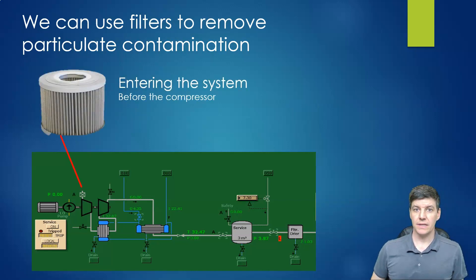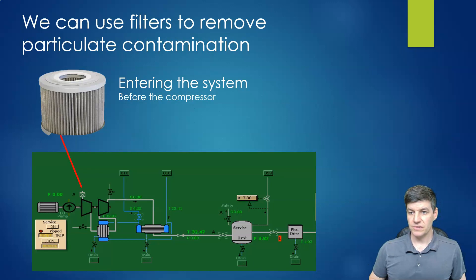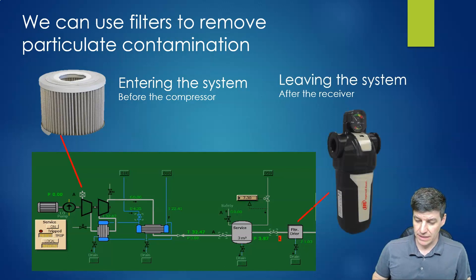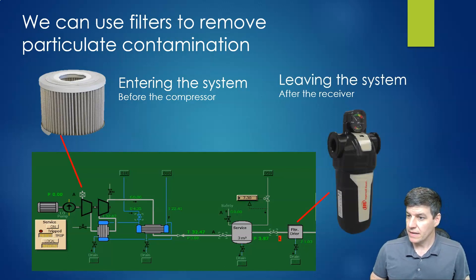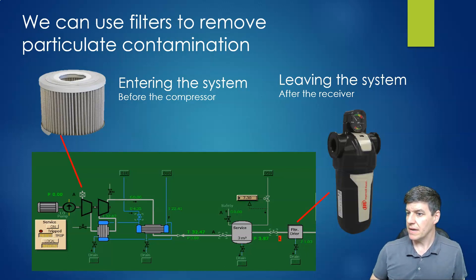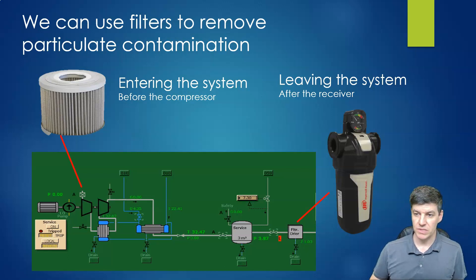Let's look at common ways in our system to remove particulates — dirt. First, on the inlet to our air compressors, we have a filter — some sort of barrier that prevents dirt from getting in, shown as a box with a little X on it. We also have a filter dryer later in the system. The filter has to be able to withstand high pressures, so it's a more robust canister. Filters protect all downstream components from dirt and other contaminants.